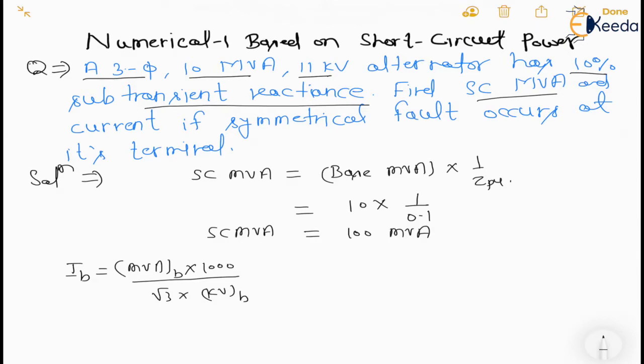You can directly apply this formula or you can calculate via conventional method S is equal to root 3 VLIL. So IB will be equal to 10 into 1000 upon root 3 into KVB means 11 KV. So this is 0.5248 kilo ampere.